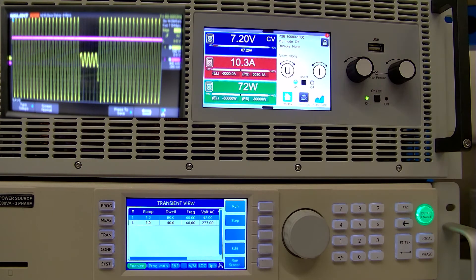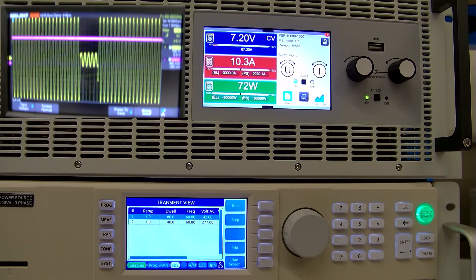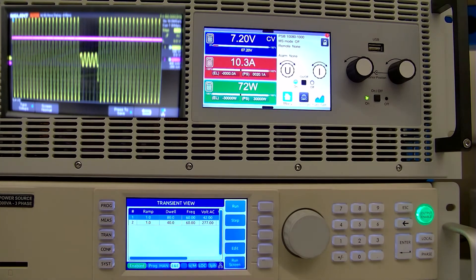So if you're in a region where you might experience some voltage sags or dips, our equipment should be able to ride through that depending on how long the requirement is. Generally only about 20 milliseconds is required, and we're about three times that. If I was to increase this a little bit longer, you would get what's called a PF or power fault on the input.